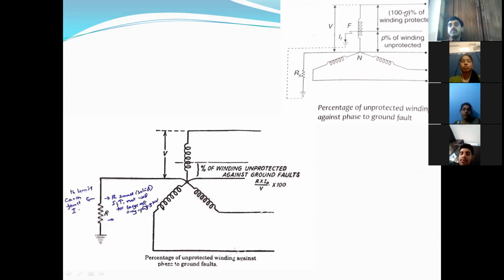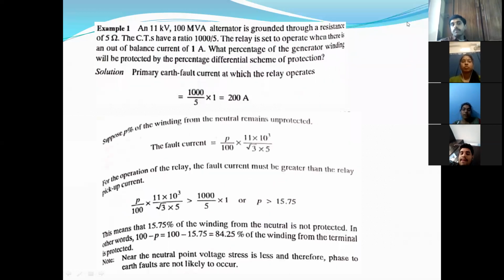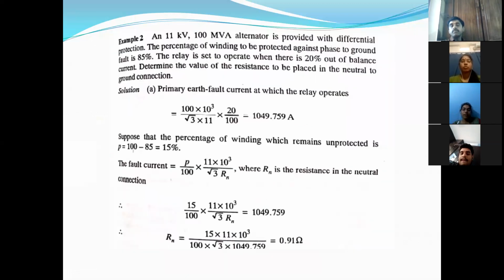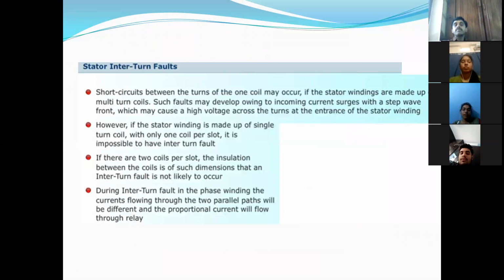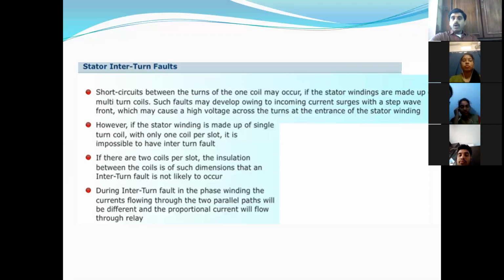Sometimes they may ask what is the percentage of winding protected. So this is all about differential protection. That means stator faults with differential protection and restricted fault protection. Let us see one more topic here, stator interturn faults, because these also come under stator faults. Already we have seen phase to ground faults and phase to phase faults. In the phase to ground faults, you have seen the restricted earth faults, and now the stator interturn faults.